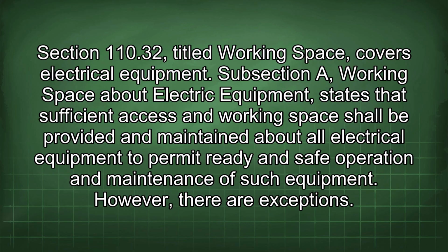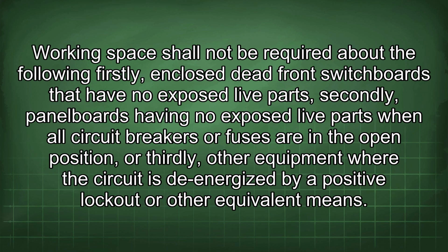However, there are exceptions. Working space shall not be required about the following: firstly, enclosed dead front switchboards that have no exposed live parts; secondly, panel boards having no exposed live parts when all circuit breakers or fuses are in the open position; or thirdly, other equipment where the circuit is de-energized by a positive lockout or other equivalent means.